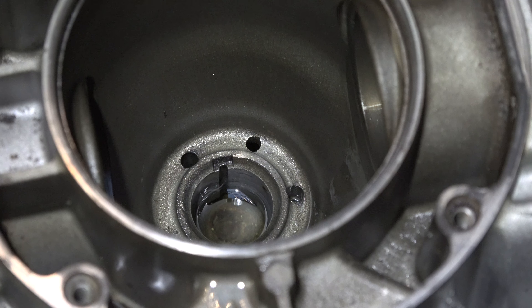The oil pump is on the bottom, so it should have been able to pull oil up out of there. But it probably couldn't pull enough oil all the time — a lot of times on startup the level gets dropped. Being that it's only about halfway up, I'm thinking it just didn't get enough oil up through the crankshaft.